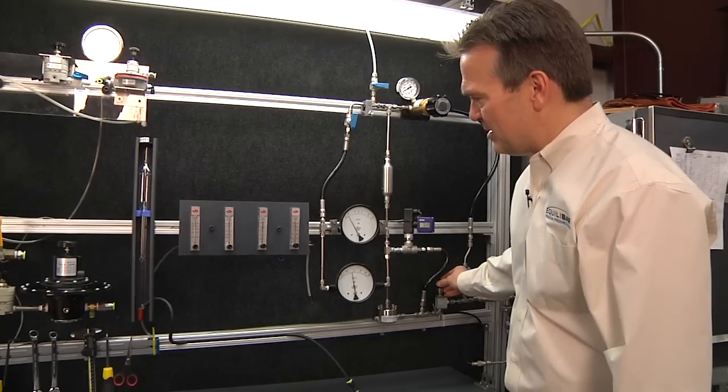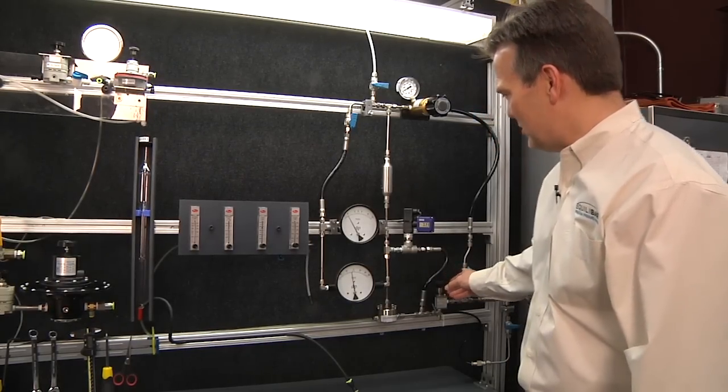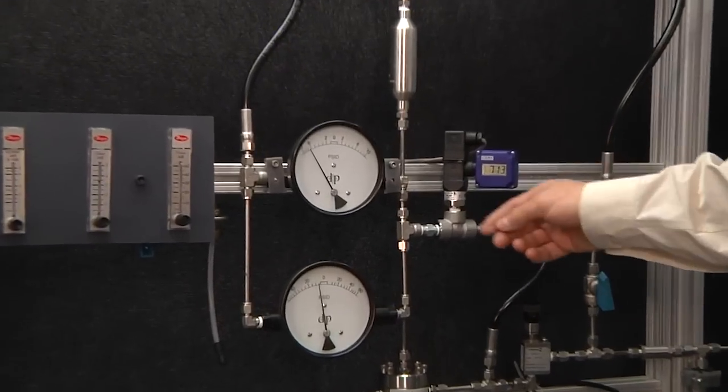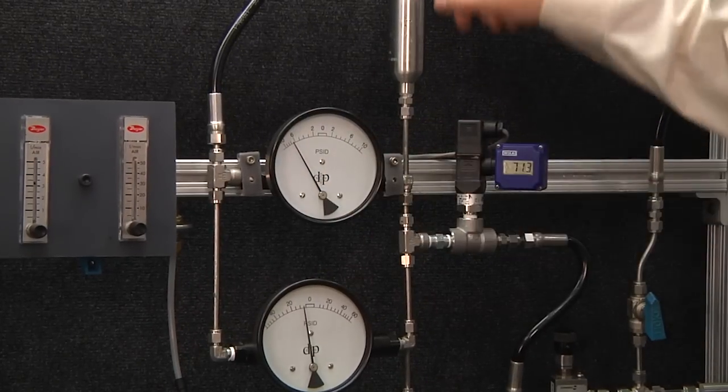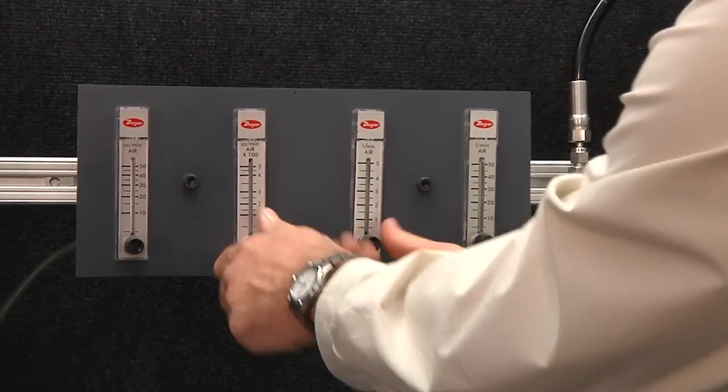Right now we have about 4,000 cc's per minute or 4 liters per minute passing through the ZF regulator. The inlet is about 713 psi and we're about 7 psi above the gas pilot pressure. What we're going to do is step that down a decade at a time.